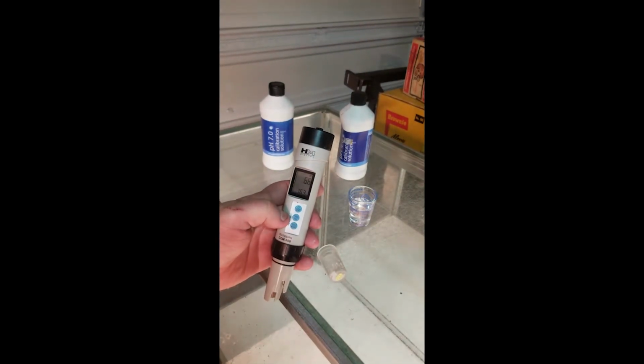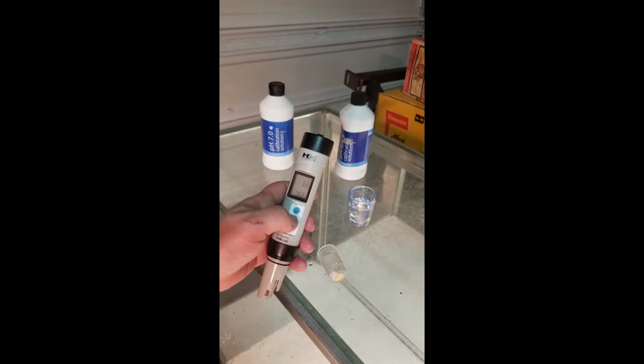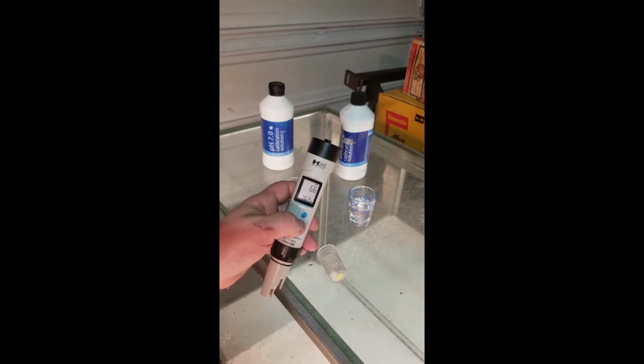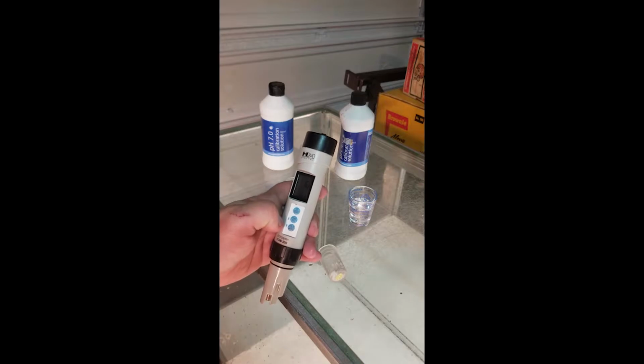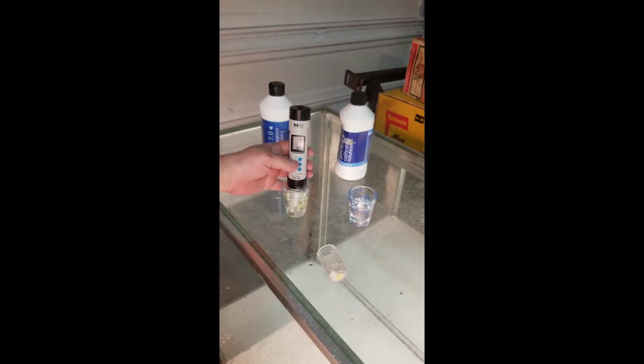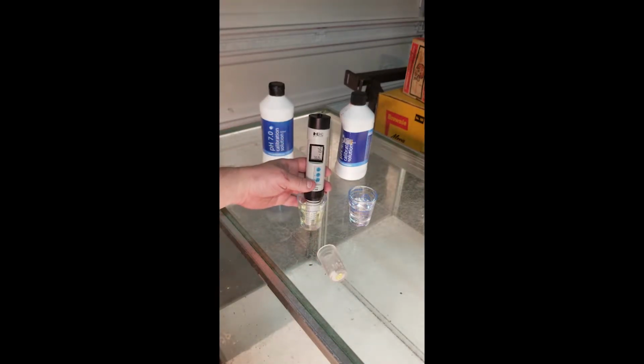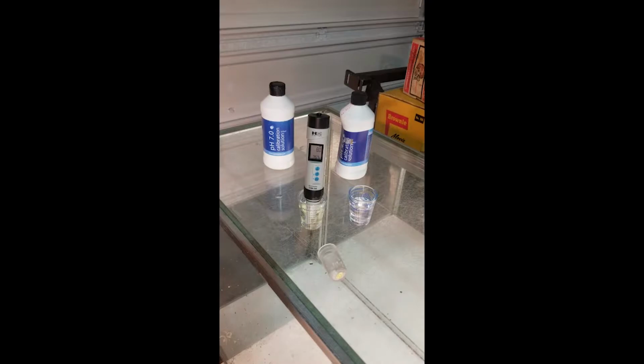This one's 6.6. It should be calibrated, but because I'm going to do the transplant video after this, and it's going to go into the 12K, I want to make sure it's calibrated. So I'm going to put it in, and you can see that I put it into the 7, and it jumped all the way up to like 7.9, 8.0. So this one is now out of calibration. So it looks like it's stabilized at 8.0, 8.1.